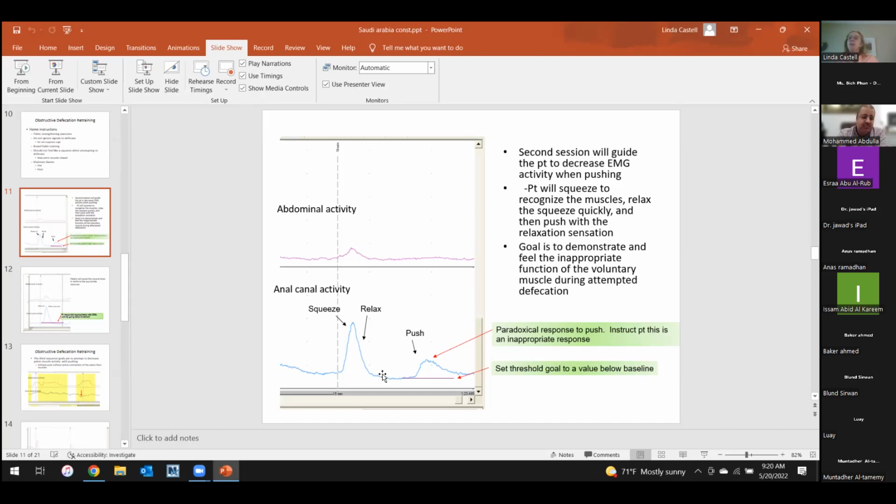Yeah, I know. And there are different pressures throughout the rectum too. Do you have the high resolution manometry catheter? Is that the catheter you're using? Yes. So when you put all 23 of those sensors inside the rectum, there are different pressures throughout the rectum, and you've got the valves of Houston. There might be a little bit of stool in the rectum pushing up against your sensors. And then as you start to pull out your catheter and get into the anal canal, the pressures are all over the place sometimes.